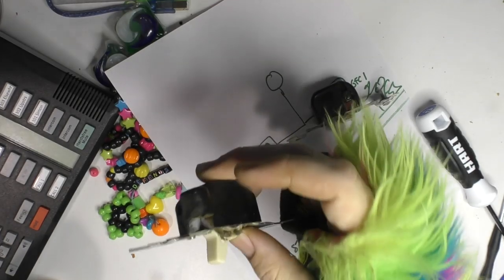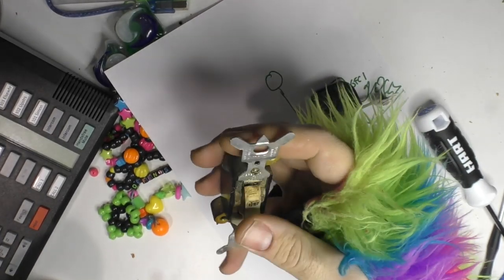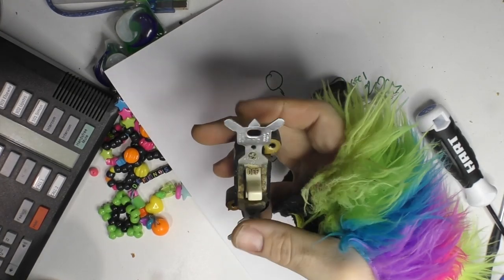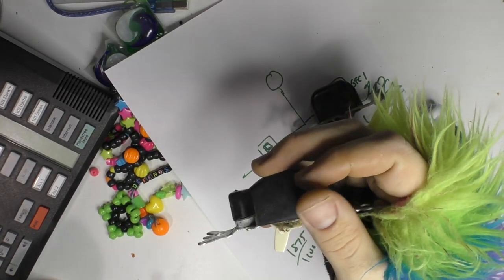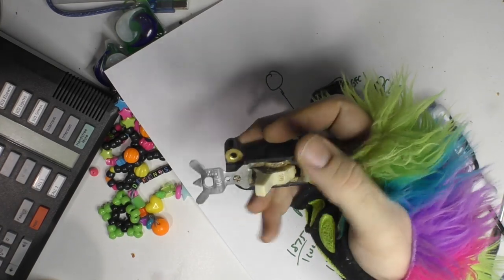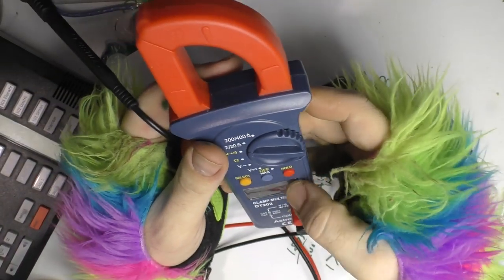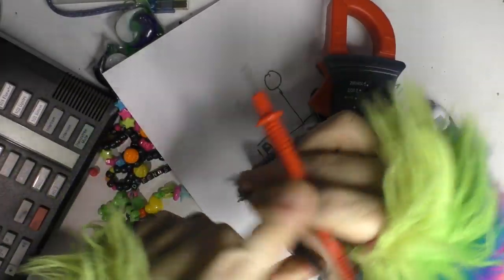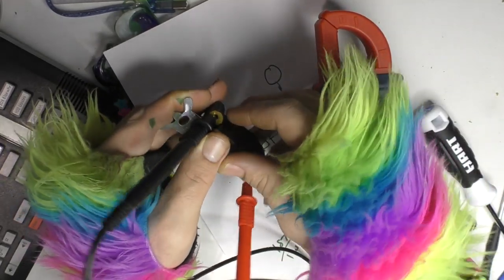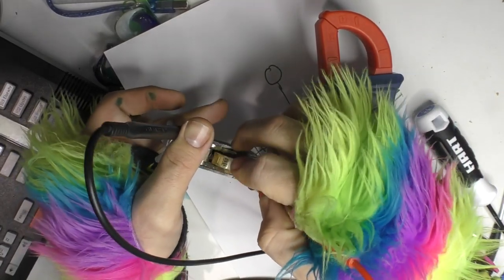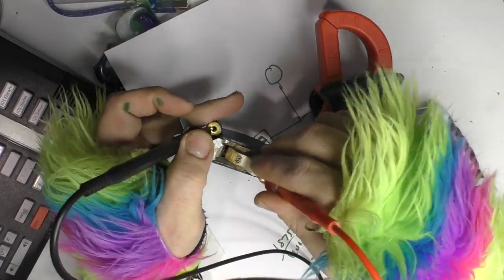So the next thing I want to find out is whether or not in whatever position this switch is in, if it actually works, if there's actually continuity through it. It's very possible the contacts have welded themselves shut or have been damaged and are completely open regardless of the position of this. Because this feels fucking chintzy. This doesn't feel like it's moving anything. So I'm going to put my meter in continuity mode. Hopefully that works. At least that we can check. I'll put it in beep mode. So it makes a beep when we have continuity. So I'm going to put these in here and here. And we have no continuity. And we have no continuity even when the switch is on. Which makes sense because even after I reset the circuit breaker, the light did not come on. So the switch is complete toast.